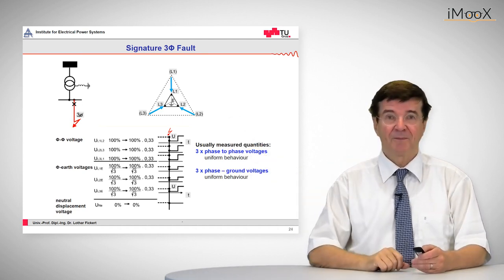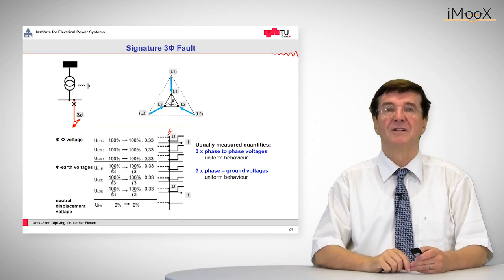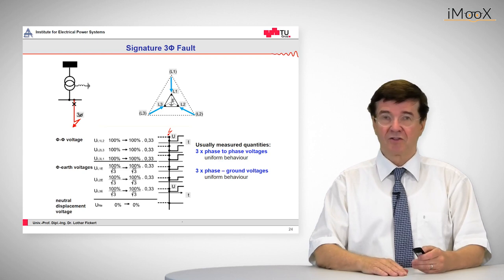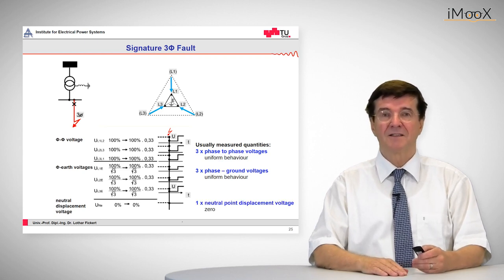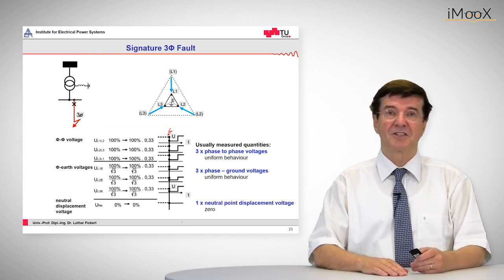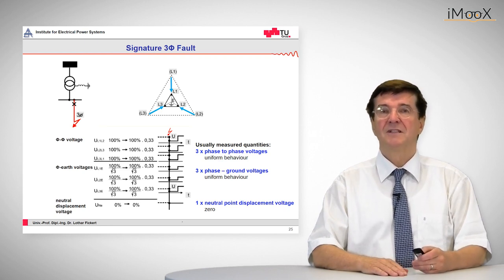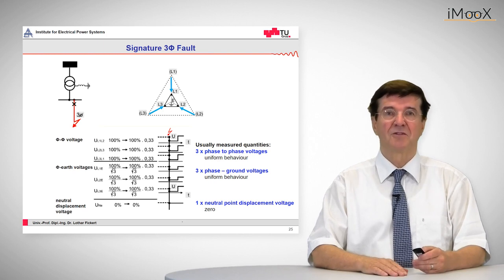The same happens to the second set of voltages, that is the phase-to-ground voltage. So these voltages also collapse uniformly and the third trace which is the neutral displacement voltage does not collapse at all because zero sequence is not involved in such a fault.